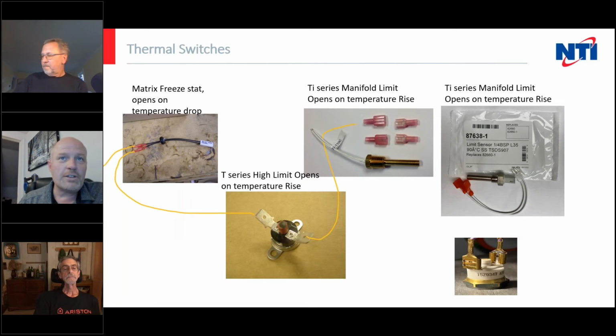So there's our wiring circuit. Now, a lot of times when we use these, we wire them in series with other safeties, which means that we go from one to the next, to the next, to the next. So if you've got a series circuit like this, the way to test it is to jumper it out one at a time. So you put a jumper across each switch individually, move on to the next switch, and in some cases you can bypass all of them for the purpose of troubleshooting only. Never leave your jumpers on.